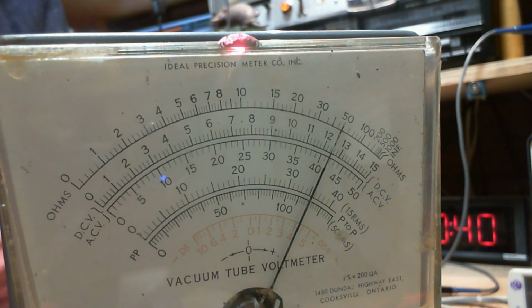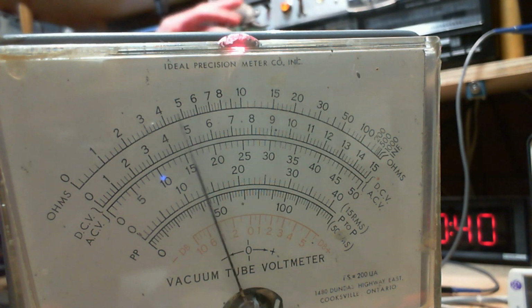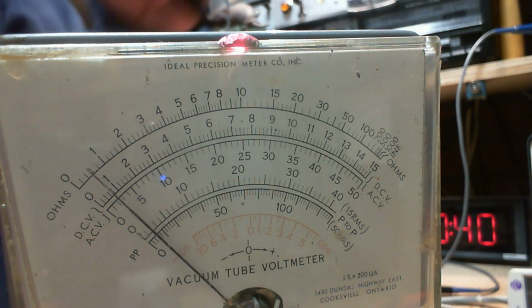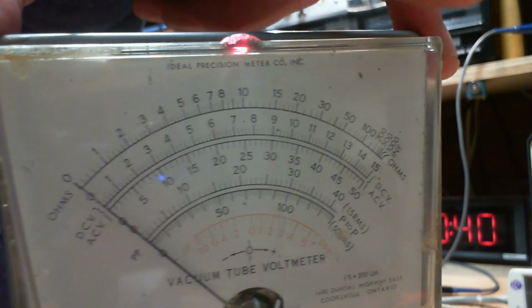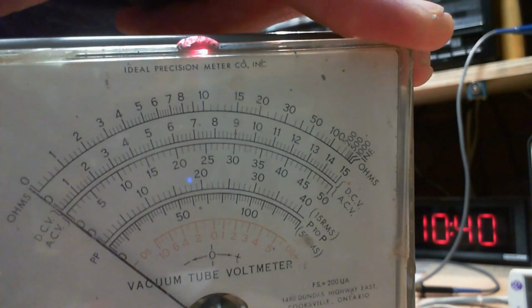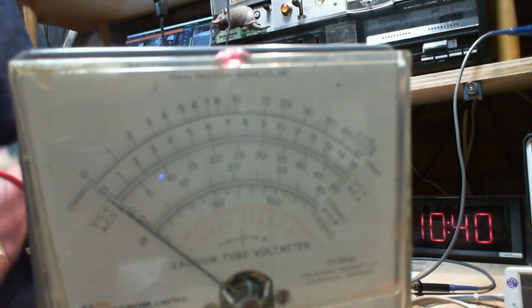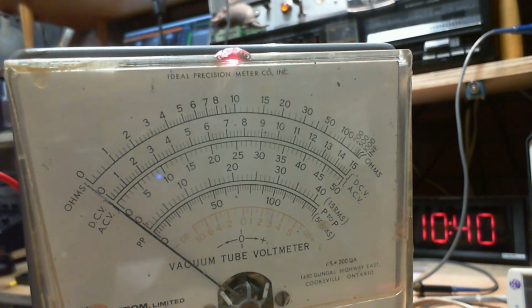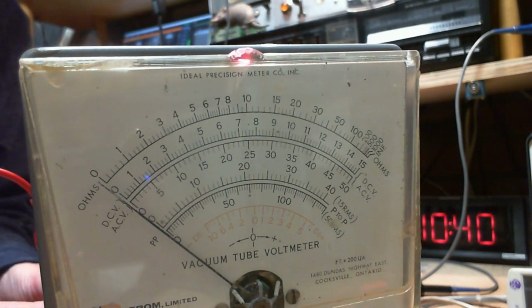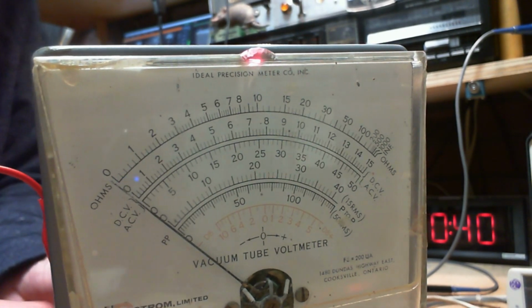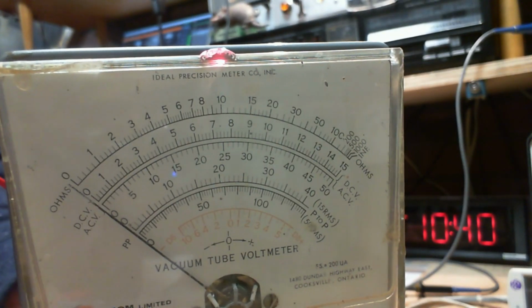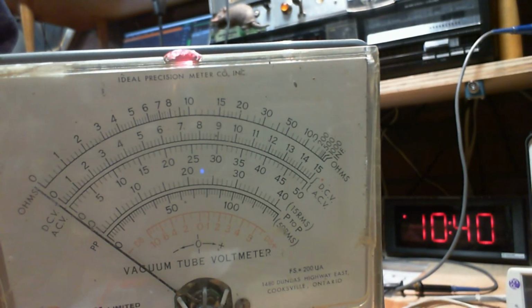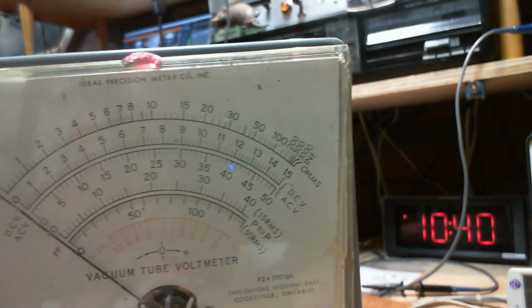So what we really want to do is AC balance. Power off. Pull the plug out. Didn't I do that already? I did this already, didn't I? Let's pull the plug out. Come on out of here. Okay. AC balance adjustment. It's from the back here. AC balance. Now this is from switching the range control from AC to DC and back.